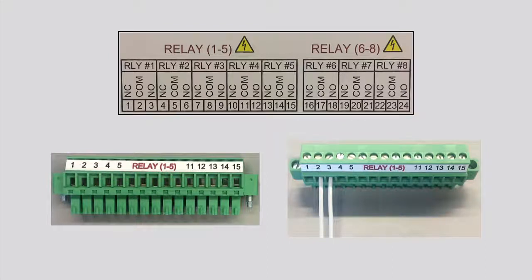The relay contacts are rated for 5 amperes at 5 to 30 volts DC or 2 amperes at 115 volts AC. Before installation, verify that the relay contacts meet the power requirements of the circuit with which it is being interfaced. In cases where the interfaced circuit demands relay contacts with a higher power rating, an interposing relay is required.